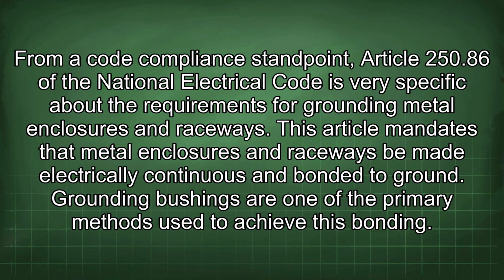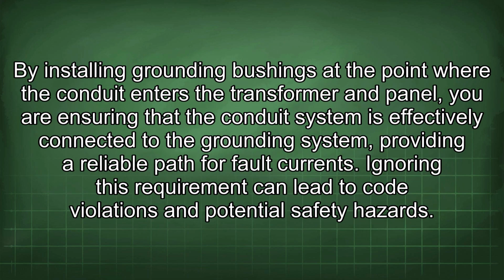From a code compliance standpoint, Article 250.86 of the National Electrical Code is very specific about the requirements for grounding metal enclosures and raceways. This article mandates that metal enclosures and raceways be made electrically continuous and bonded to ground. Grounding bushings are one of the primary methods used to achieve this bonding. By installing grounding bushings at the point where the conduit enters the transformer and panel, you are ensuring that the conduit system is effectively connected to the grounding system, providing a reliable path for fault currents. Ignoring this requirement can lead to code violations and potential safety hazards.